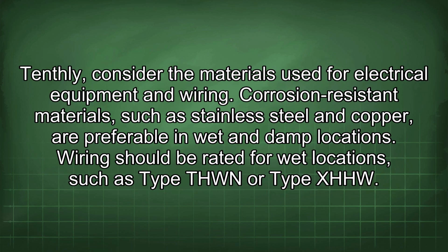Tenthly, consider the materials used for electrical equipment and wiring. Corrosion-resistant materials, such as stainless steel and copper, are preferable in wet and damp locations. Wiring should be rated for wet locations, such as type THW or type XHHW.